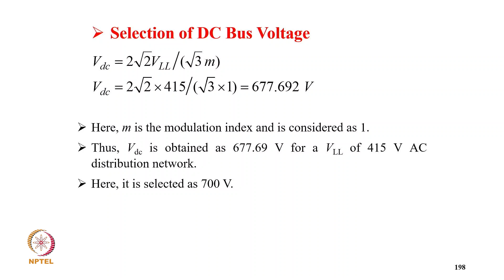it comes 76.516 ampere. Also percentage voltage ripple at DC link delta VDC equal to 5% of VDC, allowing the ripple in DSTATCOM current, so 10% of DSTATCOM current, that is 7.652 ampere. And VDC equal to 2 root 2 VLL upon root 3 M, putting a value, comes 677.692. So here M is the modulation index and is considered unity, and thus VDC is obtained as 677.692. For a VLL 415 distribution network, hence it is selected as 700 volt.